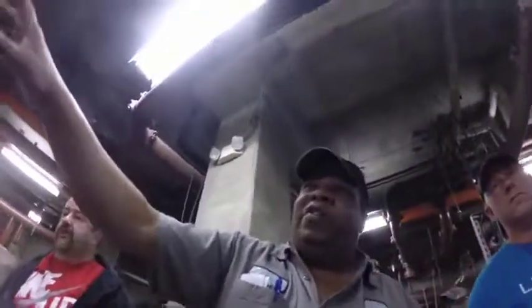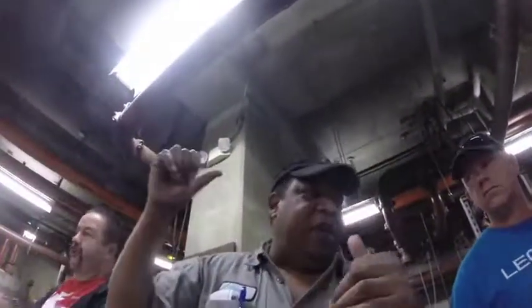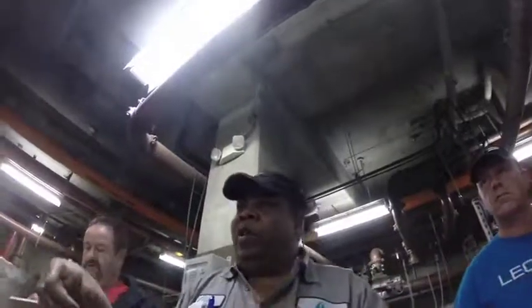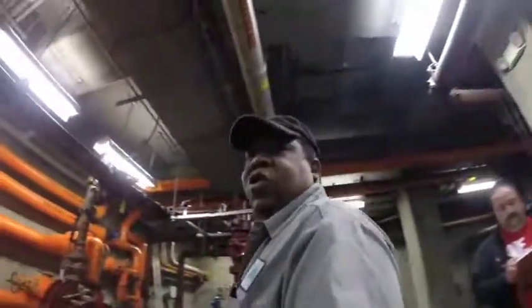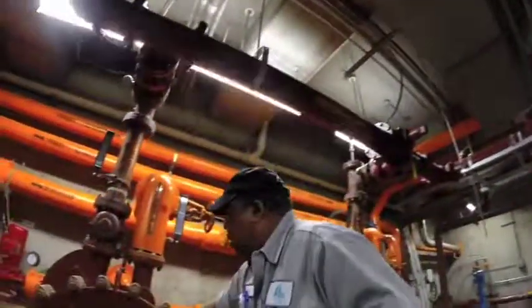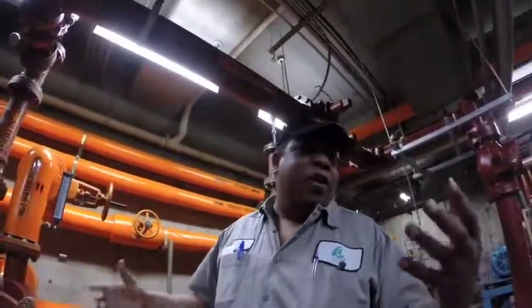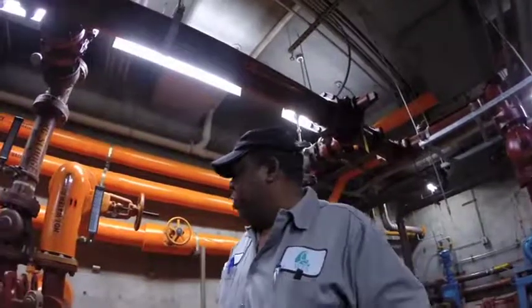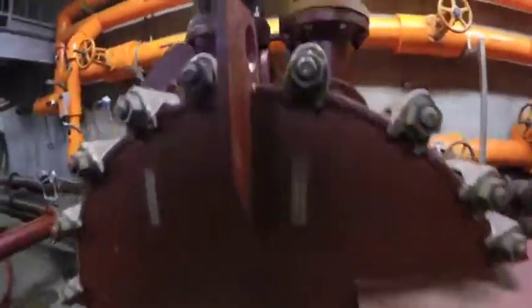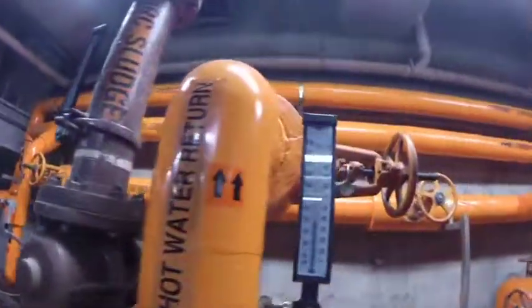All the orange lines are the hot water coming off of that engine generator upstairs, and it's being mixed through these heat exchangers right here to heat the digesters. Digesters are probably running right now about 98 degrees. These are nothing but big old Campbell soup cookers, in a big heat exchanger. That's what they are.